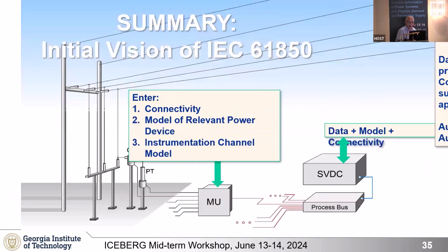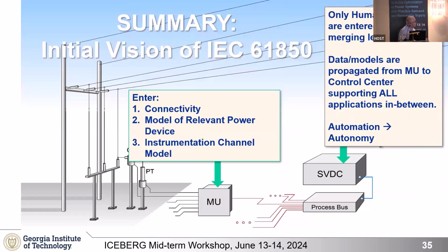So the idea is the following: we have a system where the only information we provide as a user is at the merging unit. We provide information on how it is connected to the physical system, the model of the relevant power device — if it monitors a transmission line, we provide the model of the transmission line, if a transformer, likewise — and also the instrumentation channel model. From there, the merging unit transmits this information to everything else, so the only human entry is at the merging unit. Every other component of the system, all the way to the control center, has this information, and therefore we can operate autonomously from there to the control center.